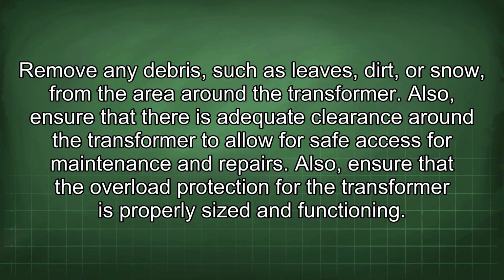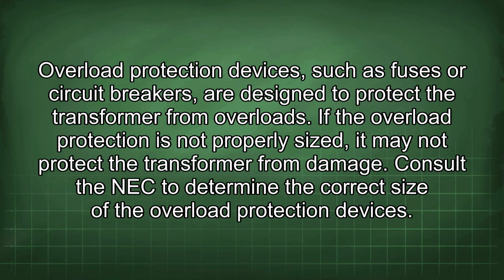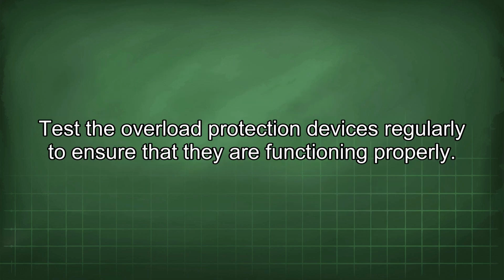Also, ensure that the overload protection for the transformer is properly sized and functioning. Overload protection devices, such as fuses or circuit breakers, are designed to protect the transformer from overloads. If the overload protection is not properly sized, it may not protect the transformer from damage. Consult the NEC to determine the correct size of the overload protection devices. Test the overload protection devices regularly to ensure that they are functioning properly.